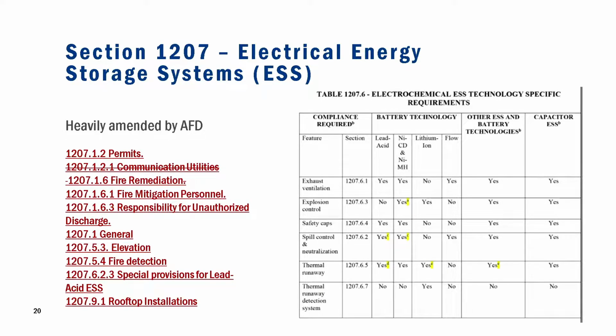This would probably exceed the purpose of this, just to introduce that there's a lot of new sections that were amended, so be aware of what those are. Then there are some specific requirements in this table regarding when exhaust ventilation is required, explosion control, spill control, and thermal runaway detection systems, which is another addition for lithium ion systems.